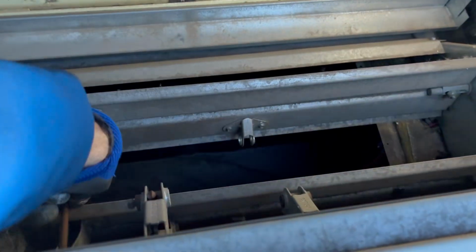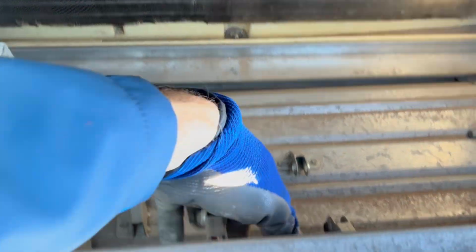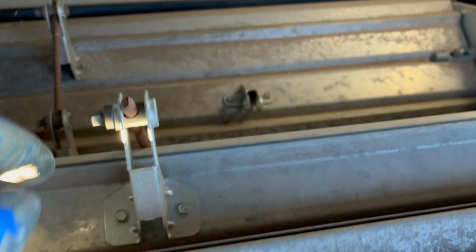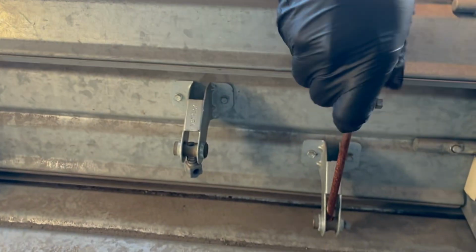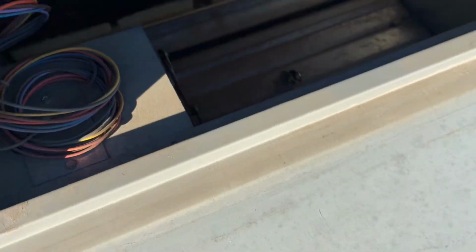The filter's removed. You can see these flaps right here, these louvers. When they're open like this, you're bringing up return air from the building through the filter, through the evaporator coil, and then down through the supply. When they're closed and this opens, if we look here, you can see you're bringing in outside air, what they call free cooling. That helps the compressor and the condenser cooling fan not run as often, so you save energy, you save money.